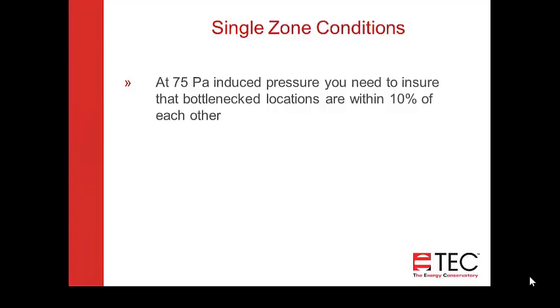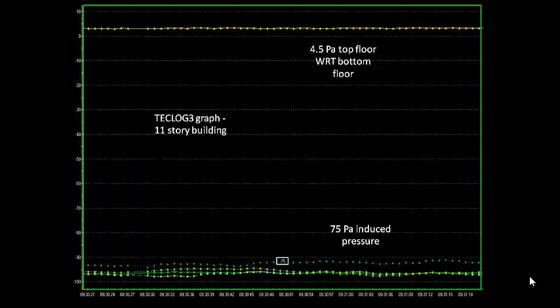At 75 pascals, you want all the pressures in the building to be within 10% of each other. As an example, we did some repeatability testing on an 11-story building and set up all the blower doors on the main level. We had two blower doors set up in a stairwell about half a flight down, and two more at the main level of the building in the front. We had an 11-story building with about 30-35 degrees outside. At the bottom of the building we were seeing 95 pascals, with a baseline of about 20 pascals, giving an induced pressure of 75.